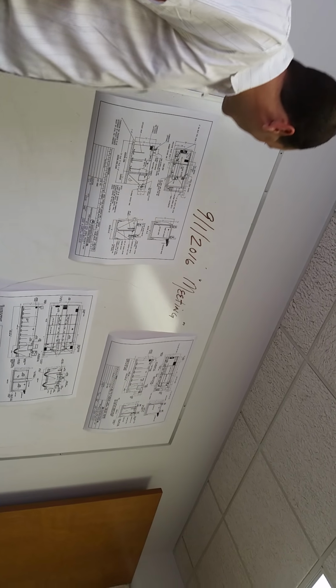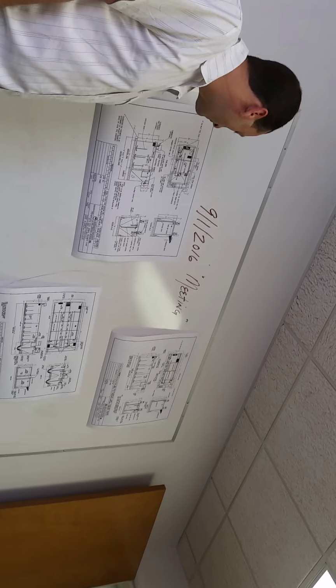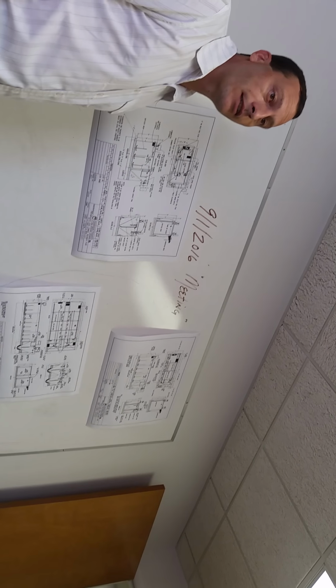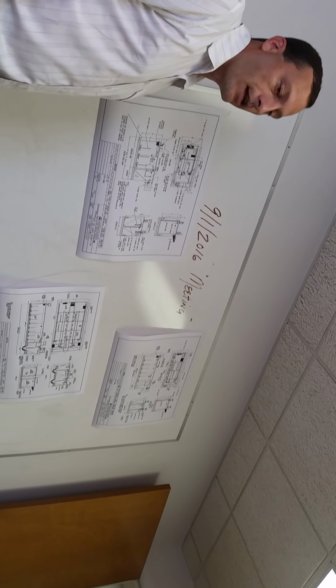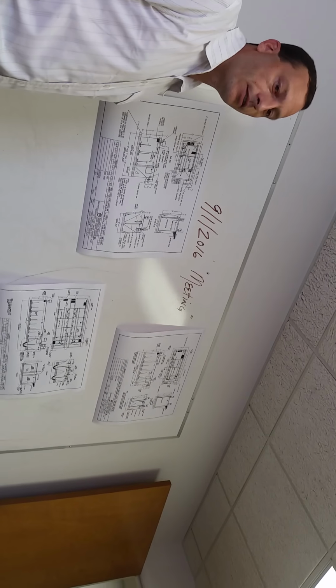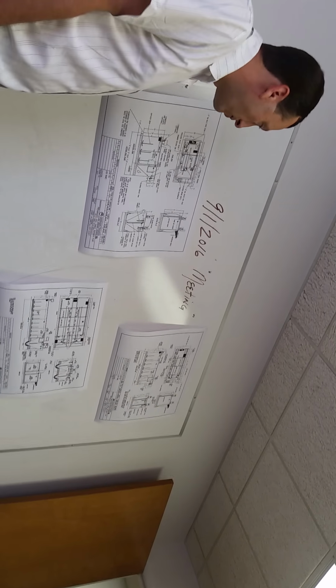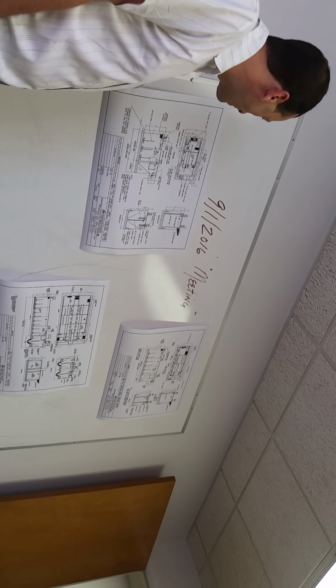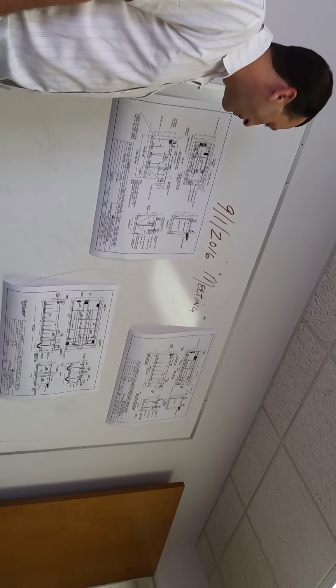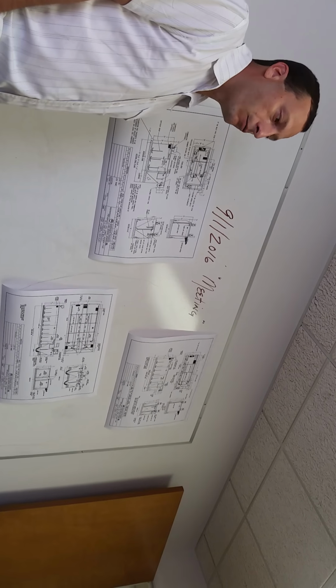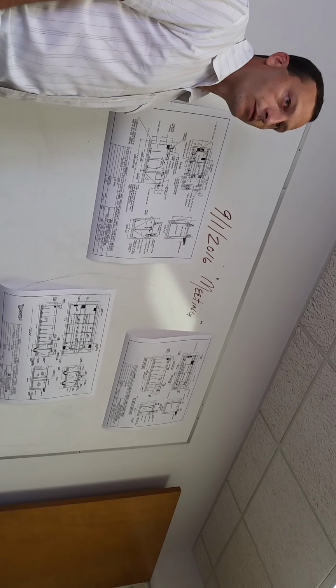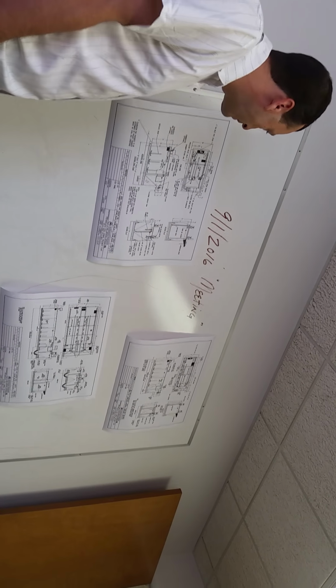So with EA, it's an older conventional style process. There's not a whole lot of variation to it. It's very easy to operate for operators in the field. There's not a whole lot you can do to mess them up. They're typically going to get you 30-30 on the way out. You're getting roughly 90% removal of your BOD and TSS.